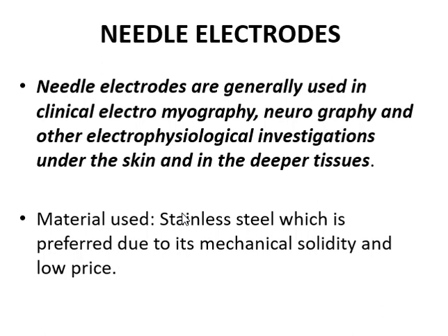Needle electrodes are used by inserting a needle electrode into the muscle, recording and amplifying the electrical signals generated from resting or contracting muscles.